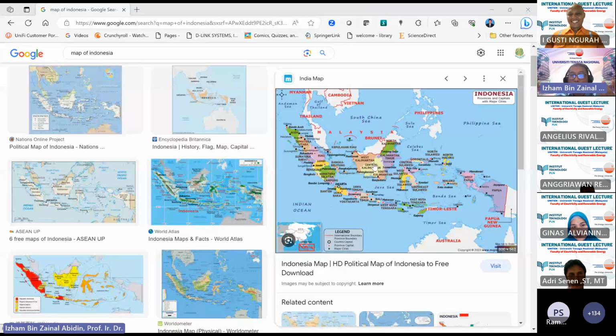But however, if you want to protect the network, say for example I want to protect Sumatra and Java, such that if Java has a bad network whereby power quality issues are bad over here, I want to make sure it doesn't go to Sumatra. Therefore I can also consider having an HVDC link over here. Or if I want to export power over long distances, let's say from Kalimantan to Sumatra or Kalimantan to Java, the distance is very long. Having an AC line may not be feasible because of the losses you might have, so you can look at HVDC links as well.